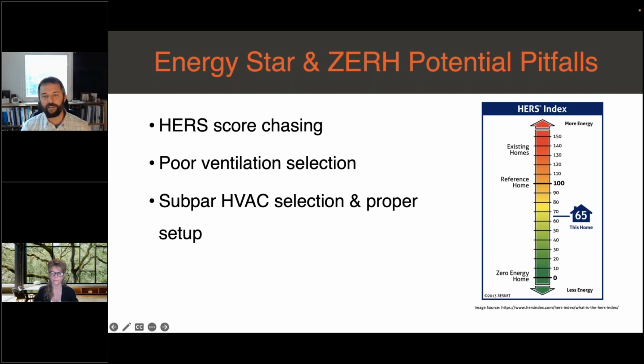A Manual J and S is not going to show you that you've selected the right equipment for part load conditions. This requires some additional performance calculations and/or modeling. That Manual J and S is selecting the equipment for the load 1% of the time. So the other 99% of the time, we need to think about.